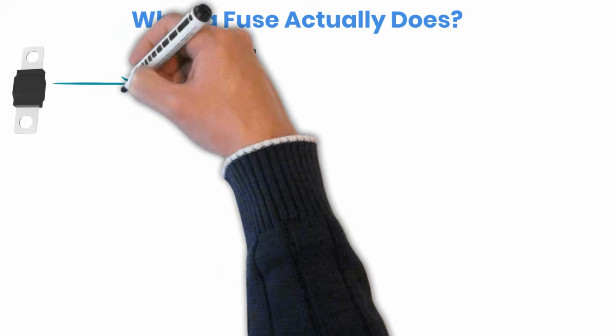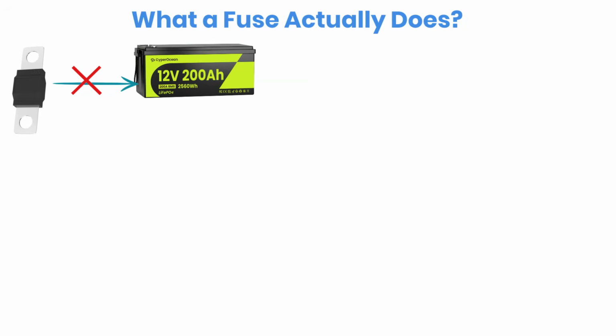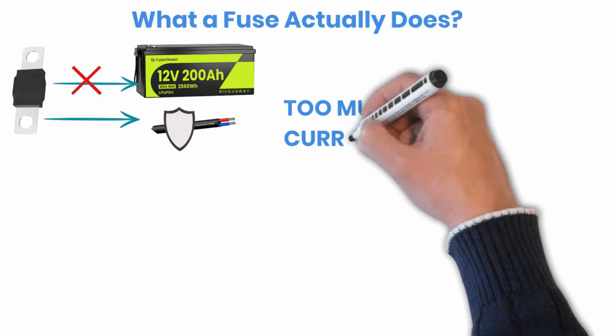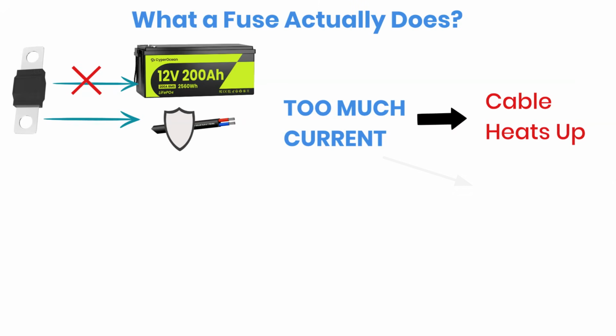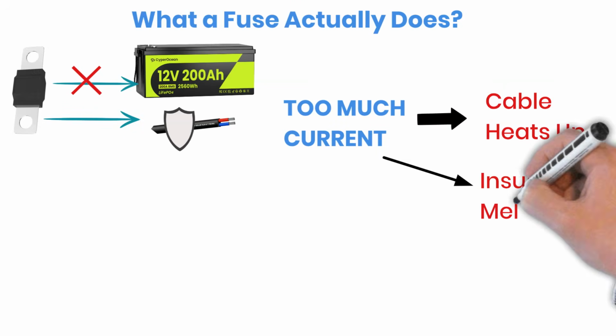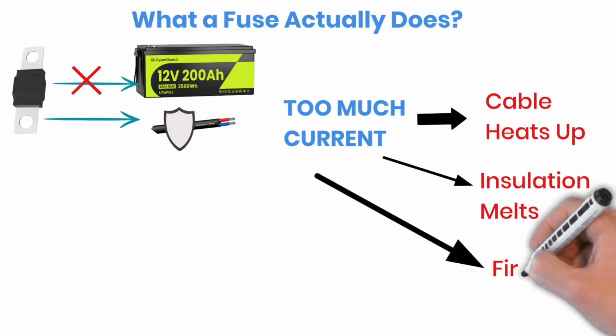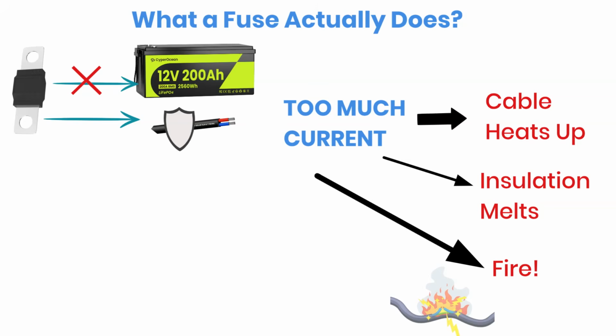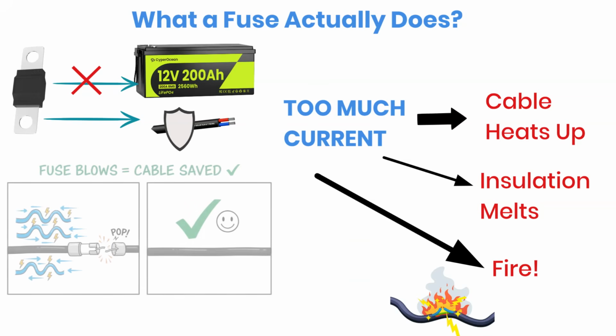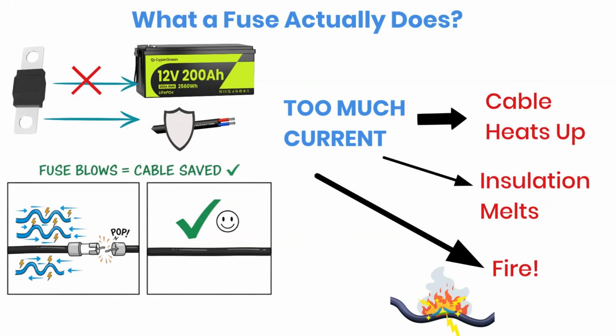First, let's fix the biggest misunderstanding. A fuse is not there to protect your battery. Its main job is to protect your cable. If something goes wrong, like a short circuit, current can shoot up extremely fast, especially with lithium batteries. We're talking hundreds or even thousands of amps in a split second. If your cable can't handle that, it will heat up, melt insulation, and in worst cases, start a fire. So the fuse acts like a safety switch. It blows early and cuts the power before the cable gets damaged. That's why choosing the right fuse is critical.